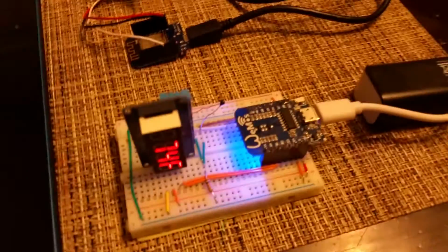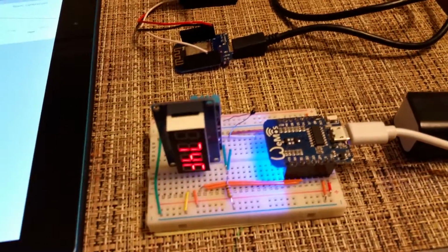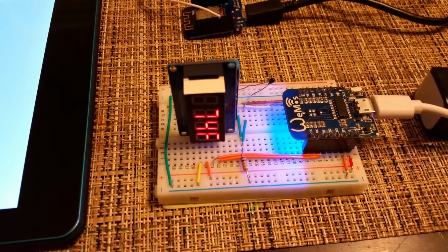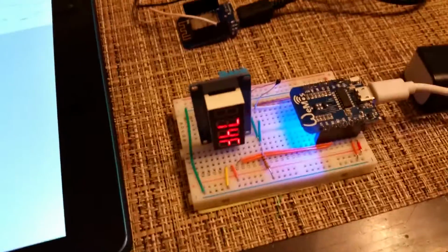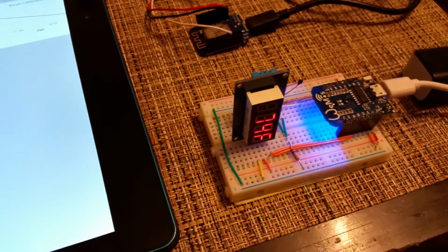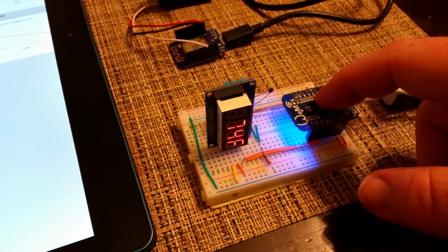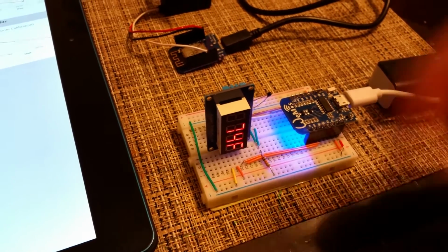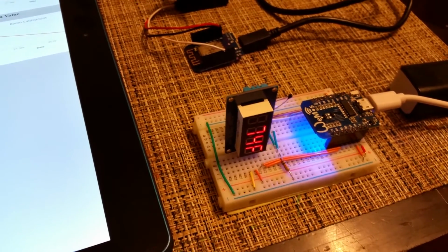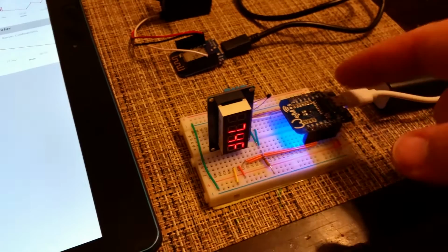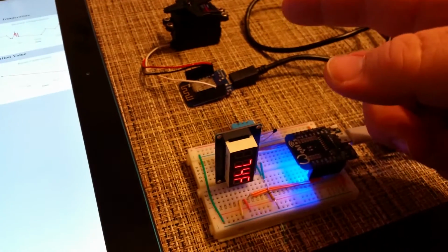Now I do have a Wi-Fi enabled thermostat, and it does run on a 7-day schedule. So one of the questions that was asked was, well, what happens if you set the temperature to a higher temperature during the day while you're at work? Well, let's say that each room has a desired temperature of 72. The Wi-Fi thermostat is going to be set to 75 while we're away at work, which means that every room's valve is going to open because it's hotter than the desired temperature. Every valve is going to be in the open position.